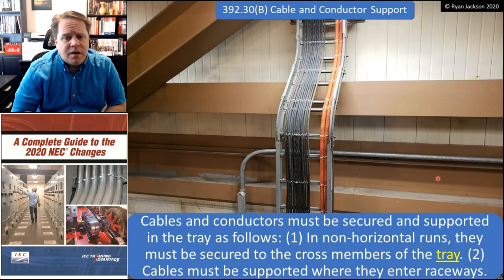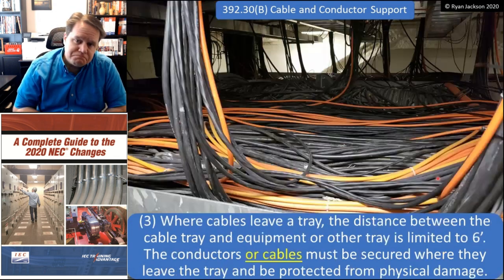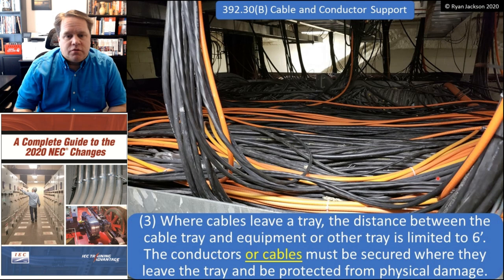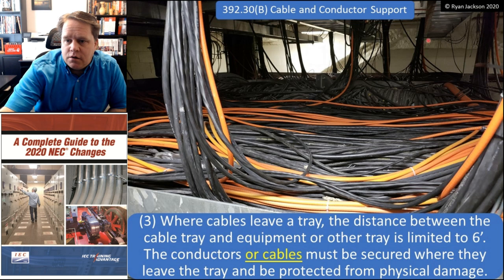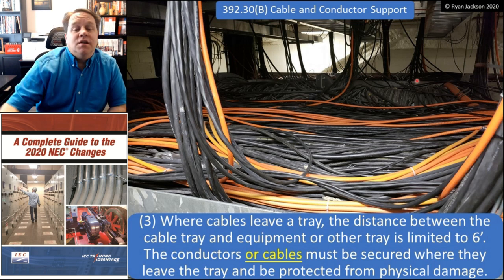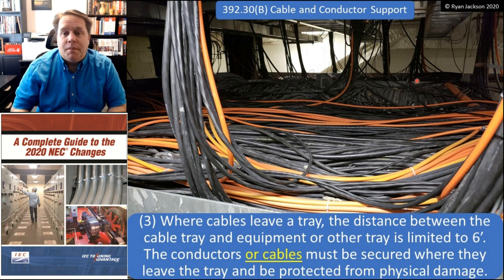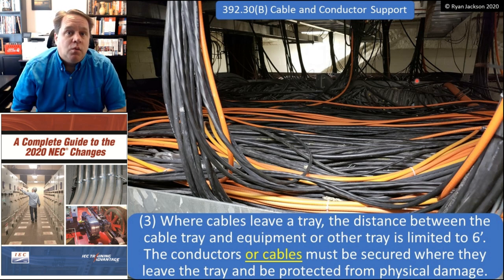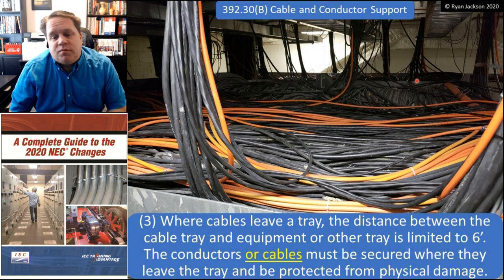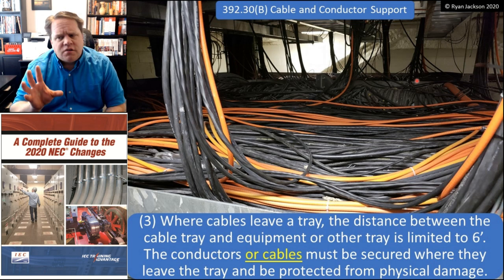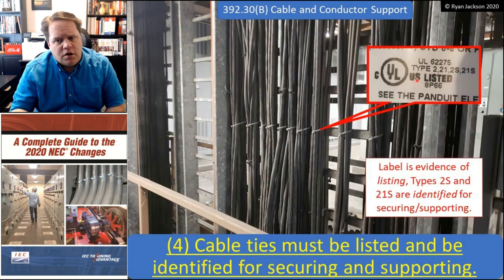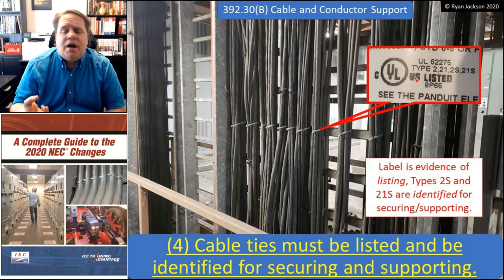Item two: cables have to be supported when they enter the raceway. Item three: where cables leave the cable tray, the distance between the cable tray and other equipment is limited to six feet — we can't just run cables down the wall with no support. The conductors or cables have to be secured where they leave the tray and protected from physical damage.